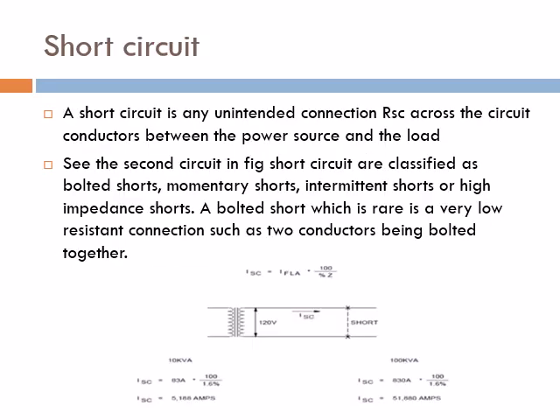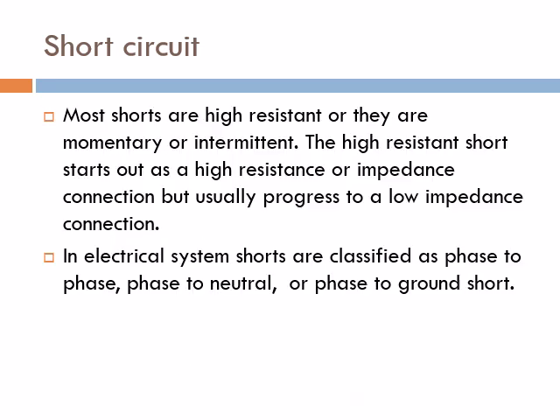A short circuit is any unintended connection across the circuit conductors between the power source and the load. Short circuits are classified as bolted shorts, momentary shorts, intermittent shorts, or high impedance shorts. A bolted short is a rare, very low resistance connection, such as two conductors being bolted together. Most shorts are high resistance, momentary, or intermittent. A high resistance short starts as a high impedance connection but usually progresses to a low impedance connection.